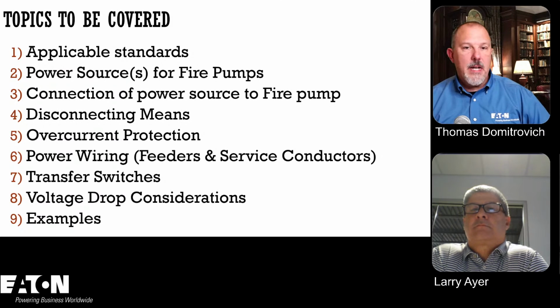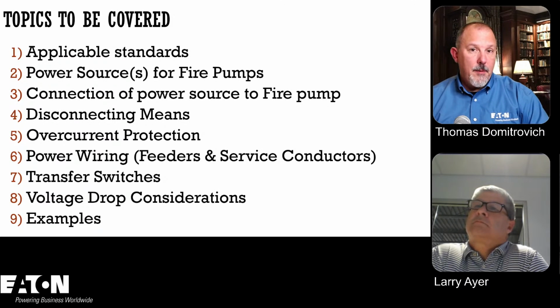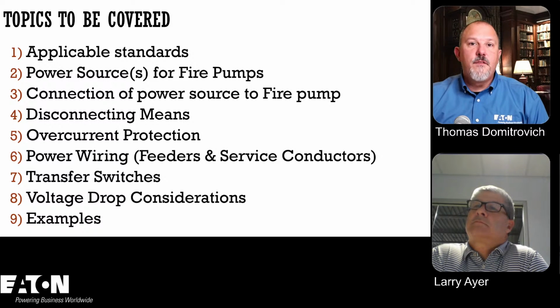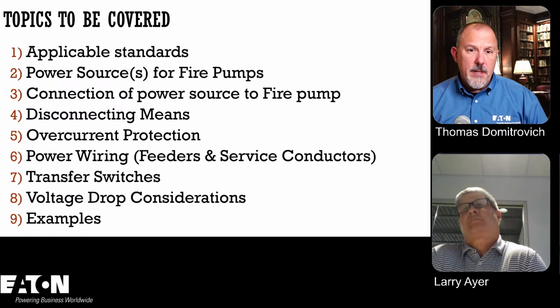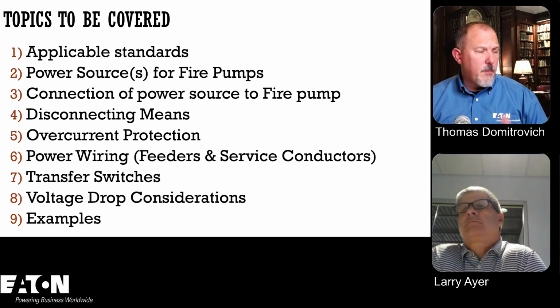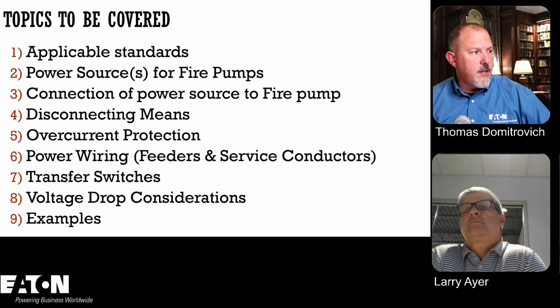So I wouldn't expect that, because if you put it outdoors, it would have to be listed for that application. But if it's indoors, I think what they're probably saying, and I don't know where that requirement is, is that you can't use a type 1, that you have to use a type 2 for ingress of solid foreign objects like falling dirt and things of that nature.